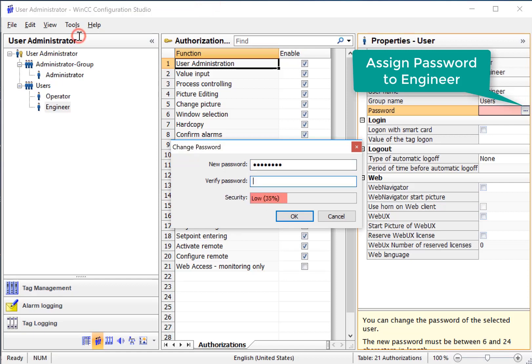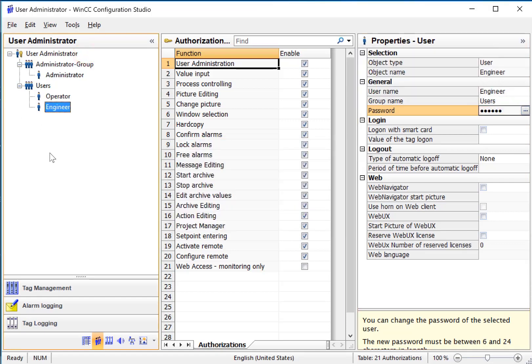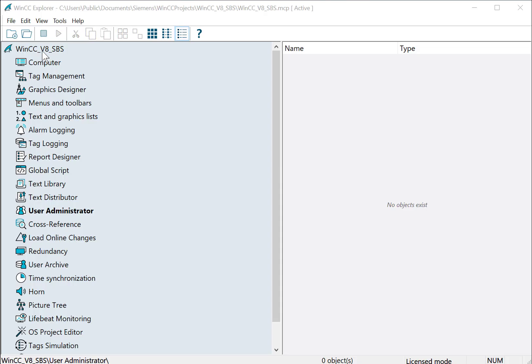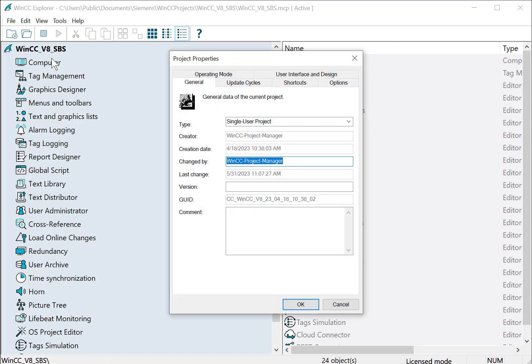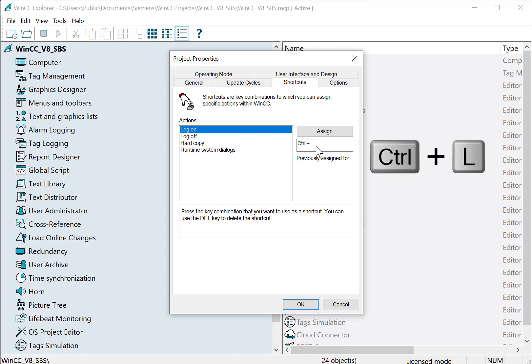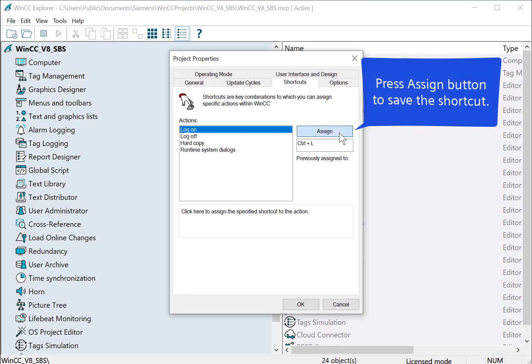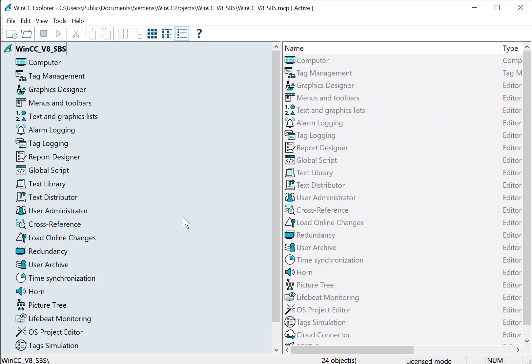So now we have our users created. Next we're going to go into WinCC Explorer and open the project properties. We will go to shortcuts and we're going to set a keyboard shortcut to logon. I'll select logon, click in this box and just hit the keystroke that I want to use and click assign. This will allow us to hit Ctrl+L when in runtime to pull up the logon dialog.